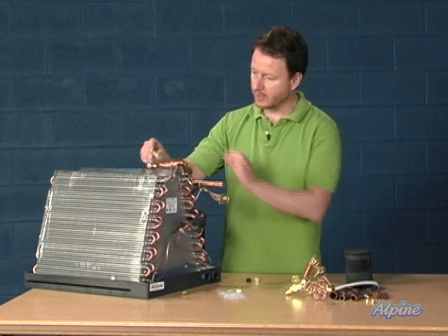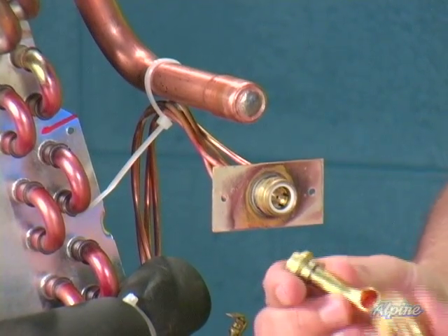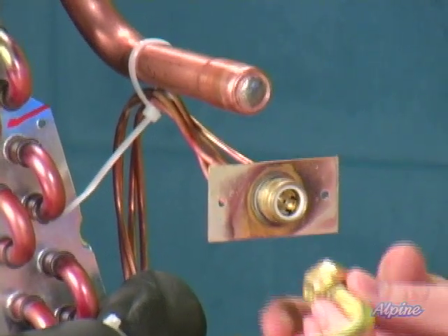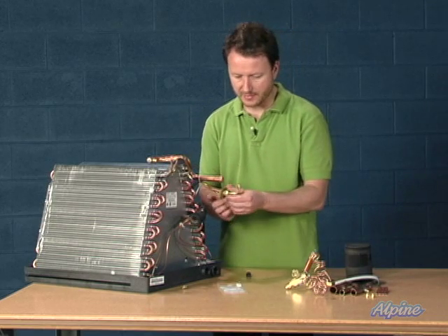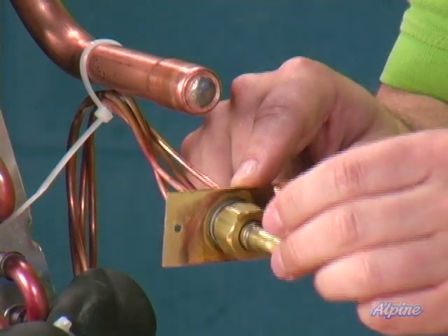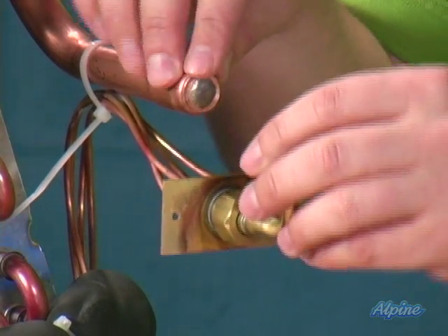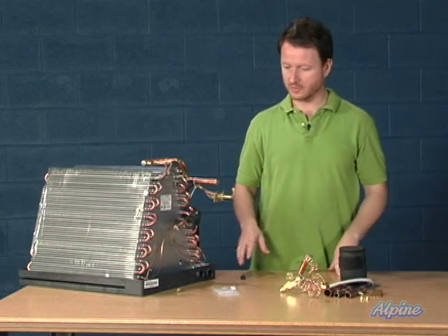And then the coil will have one of these little pipes included in it, and this flare fitting, and tighten that in place with some wrenches so it's snugged up. And then, per the normal installation, you would solder in the liquid line and the suction line set. Those are the pipes that connect the indoor equipment to the outdoor equipment, and proceed with your installation as normal.